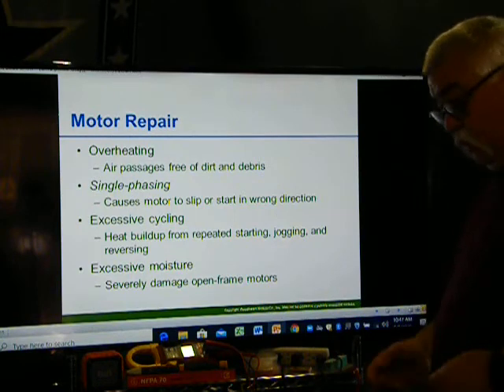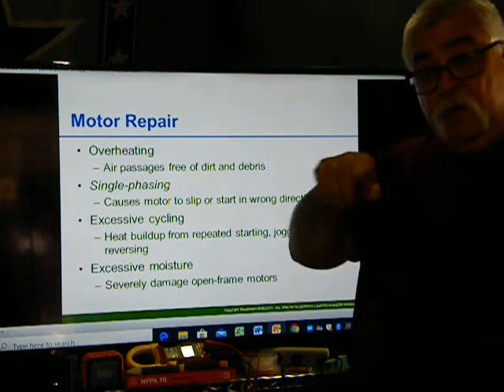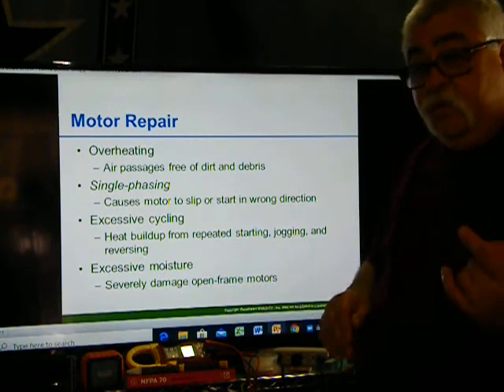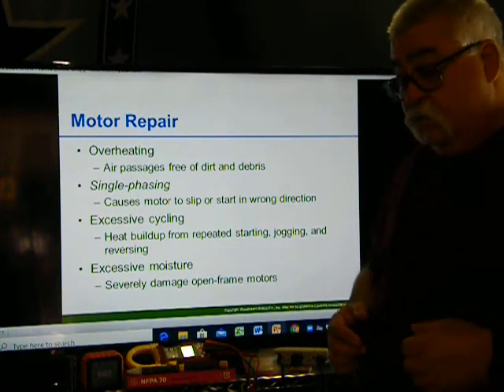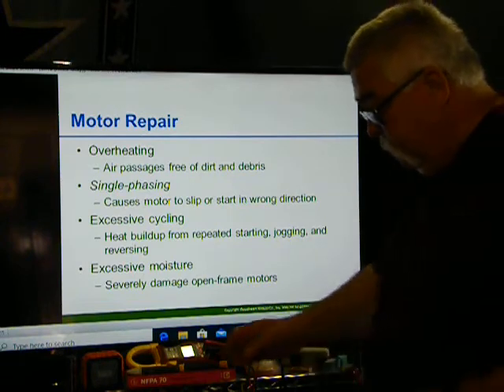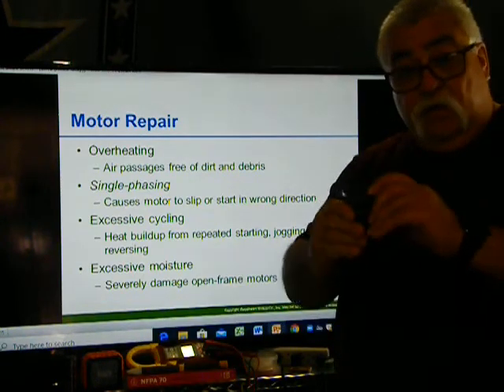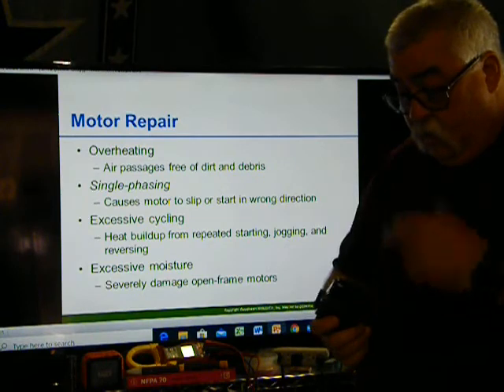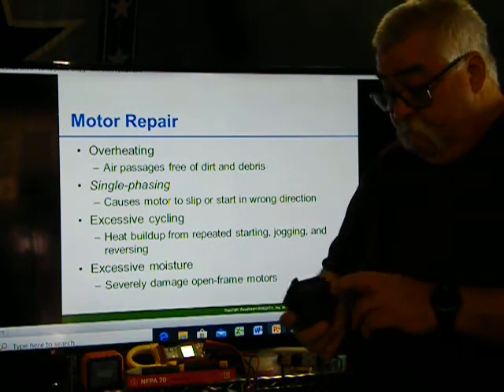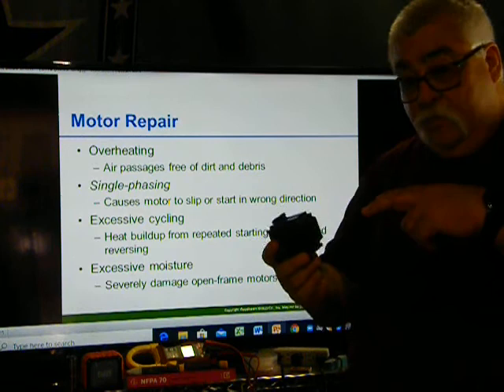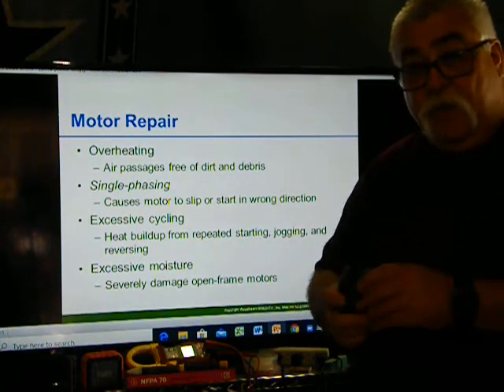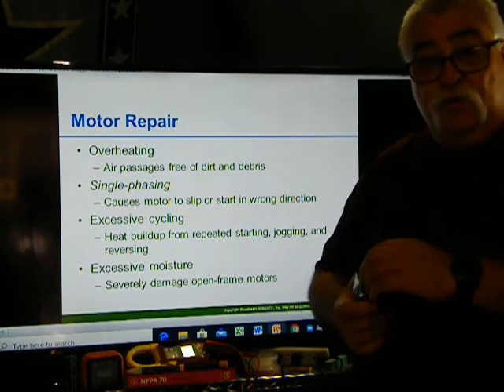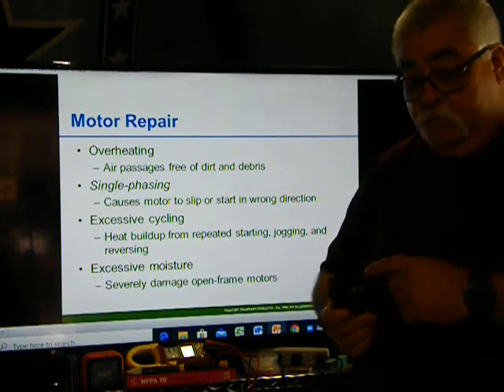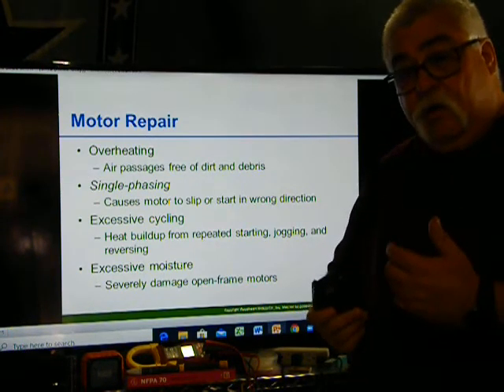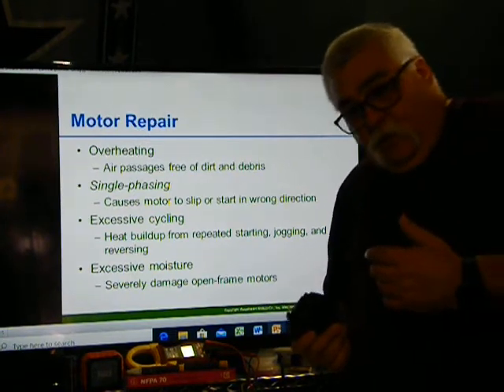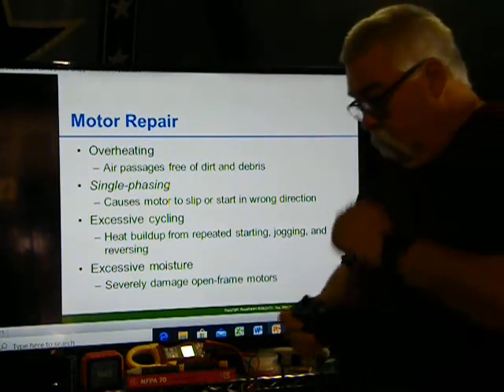So when you're doing that, hot to ground, hot to ground, hot to ground, you should get the same voltage. If you have 0 on one, then there's your problem. Either the fuse is bad or maybe the breaker went bad. Finally got a breaker today. Here's a 2-pole. I got a 3-pole back there somewhere, I just couldn't find it. But I got 2 hots coming out of here. Let's say half of this breaker goes bad internally, or the breaker tries to trip but only half of it trips. So the motor sits there with a hot on it and just tries, and it can cause excessive heating.